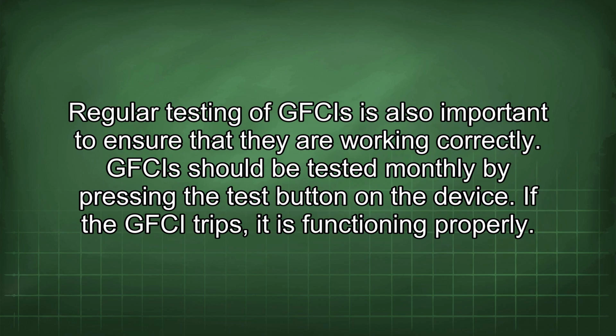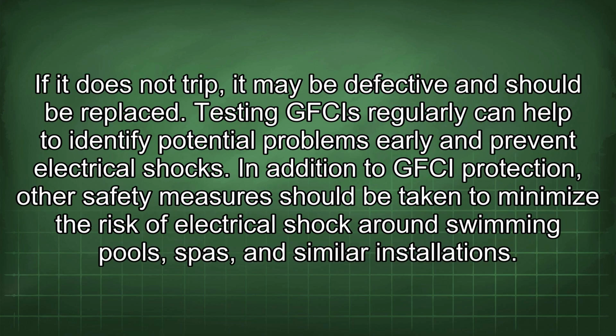Regular testing of GFCIs is also important to ensure that they are working correctly. GFCIs should be tested monthly by pressing the test button on the device. If the GFCI trips, it is functioning properly. If it does not trip, it may be defective and should be replaced. Testing GFCIs regularly can help to identify potential problems early and prevent electrical shocks.